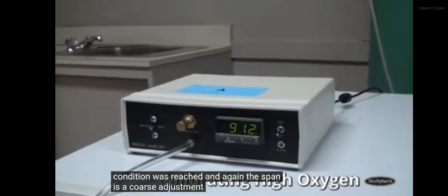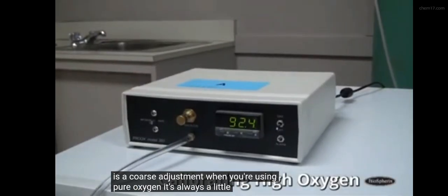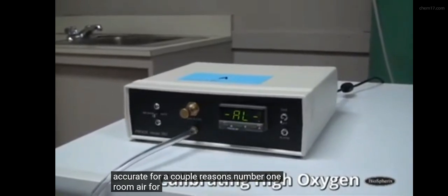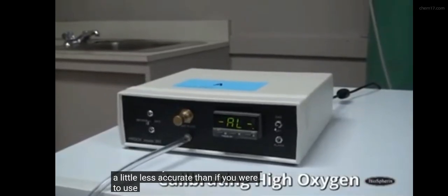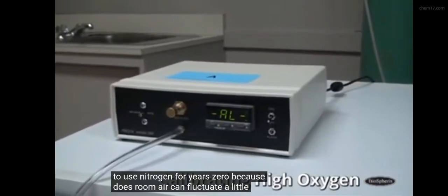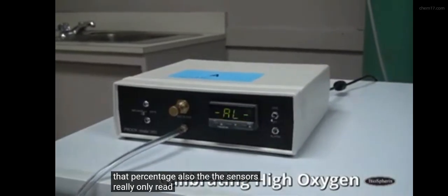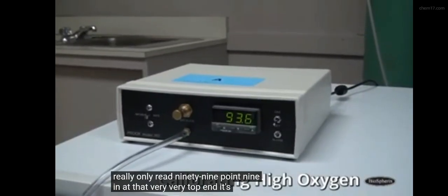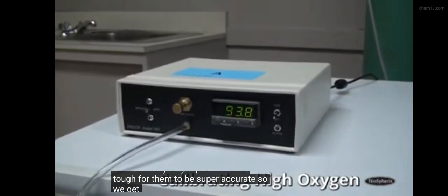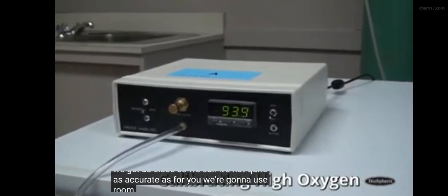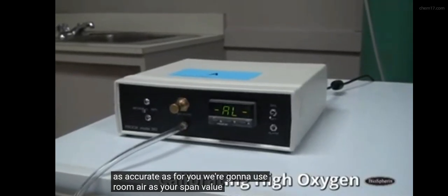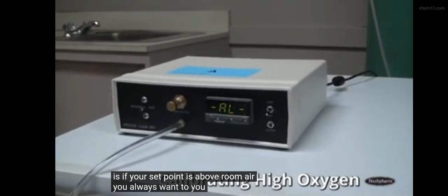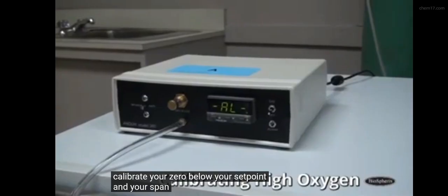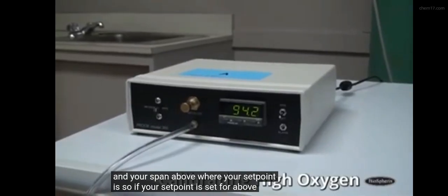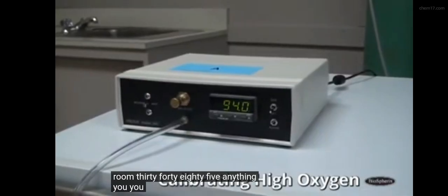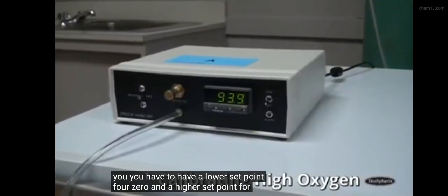And again, the span is a coarse adjustment. When you're using pure oxygen, it's always a little less accurate for a couple reasons. Number one, room air for your 0, 20.8, is a little less accurate than if you were to use nitrogen for your 0, because room air can fluctuate a little bit in that percentage. Also, the sensors really only read 99.9, and at that very top end it's real tough for them to be super accurate. So we get as close as we can. It's not quite as accurate as if you were going to use room air as your span value. But the idea is, if your set point is above room air, you always want to calibrate your 0 below your set point and your span above where your set point is. So if your set point is set for above room, 30, 40, 85, anything, you have to have a lower set point for 0 and a higher set point for your span.